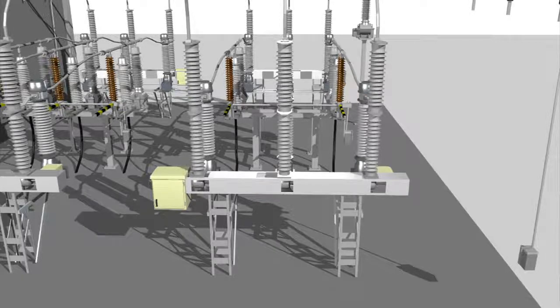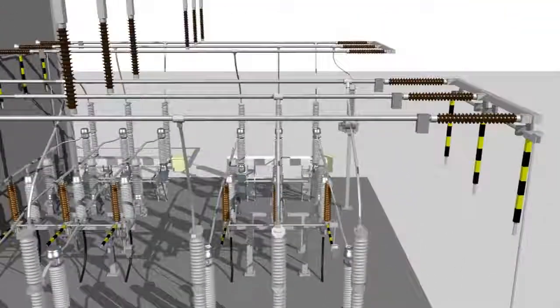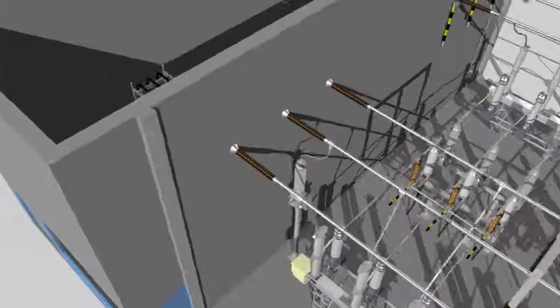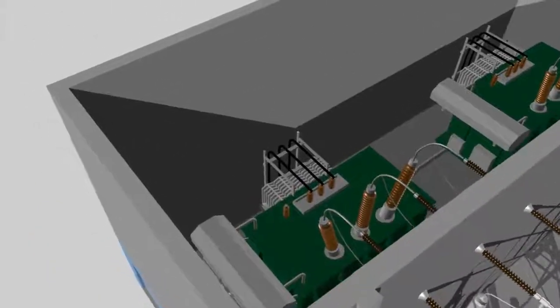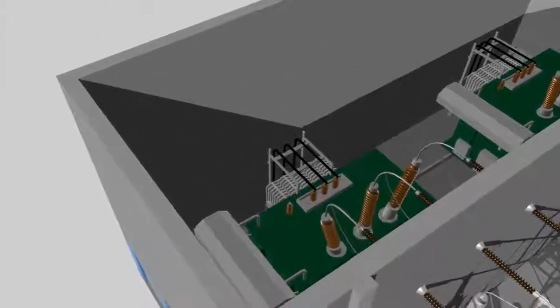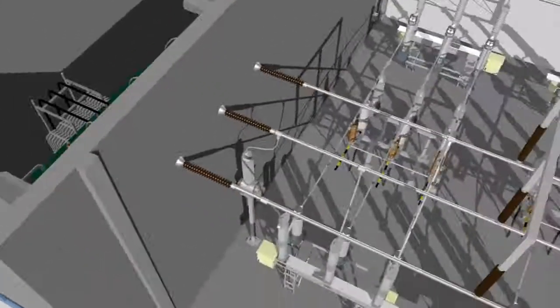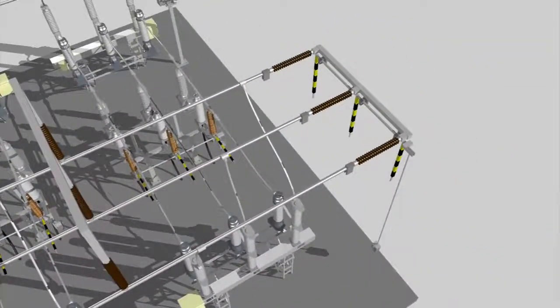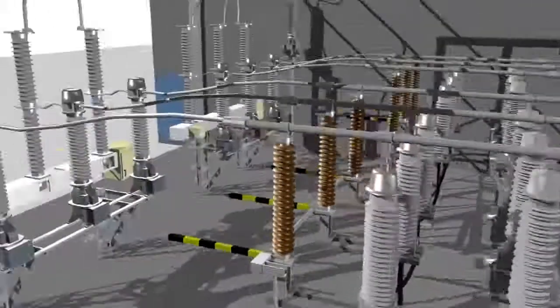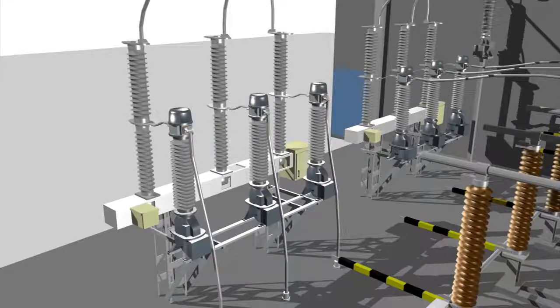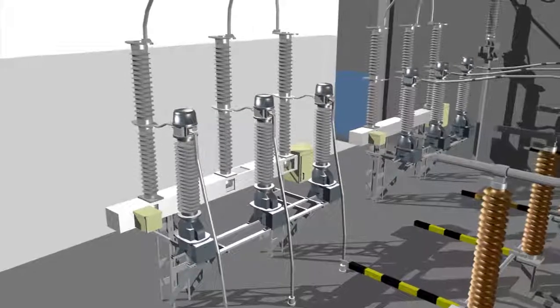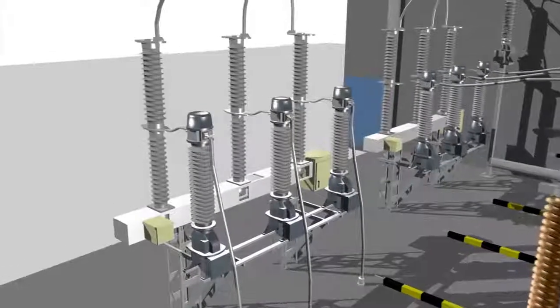The medium voltage breaker connected to the transformer is also opened and disconnected. The bus bar and transformer are now fully disconnected from the incoming line. The bus bar is thus out of service, and the motor-operated grounding switch grounds the bus bar. The links to the line entrance, which are still live, are removed. It is now safe to start working on the disconnecting circuit breaker while the line is kept in service.